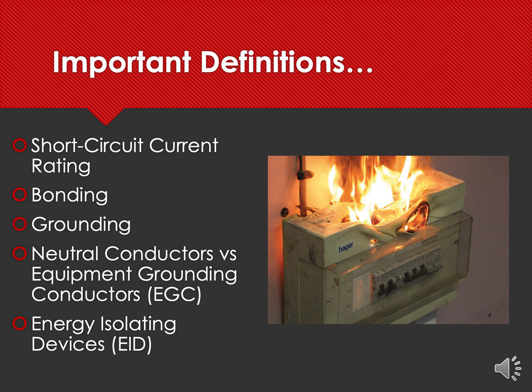We need to also differentiate between neutral conductors and what we call equipment grounding conductors, abbreviated EGC. Now, equipment grounding conductors are the same as the third prong on the plug on an extension cord. And the purpose of the EGC is to make sure that if that equipment has an internal fault, it will quickly trip the system offline so that it doesn't harm human beings working on or with that equipment. The difference between them is a neutral conductor is a purposeful current-carrying conductor. We engineer it and install it with the intent of it carrying amperes of current in the system. Conversely, the equipment grounds normally have zero current on them. The only time they have current on them is when there's a ground fault, typically in the system. Now, the key point I want you to get from this discussion is that there could be a voltage or a difference of potential between the neutrals and the equipment grounds.